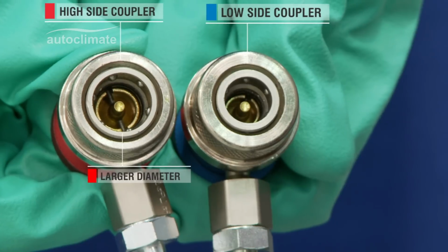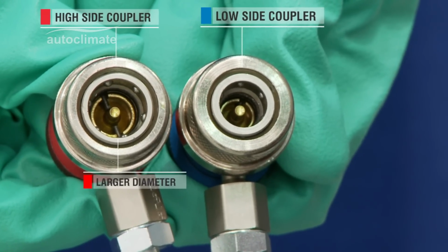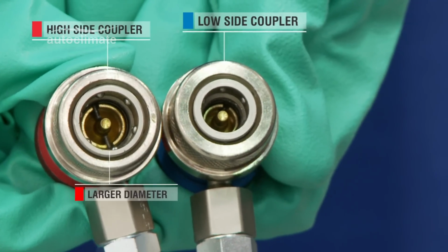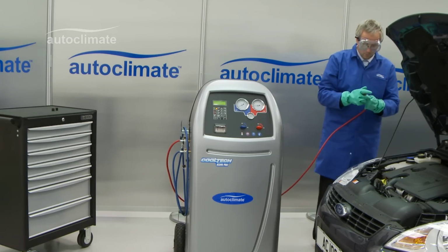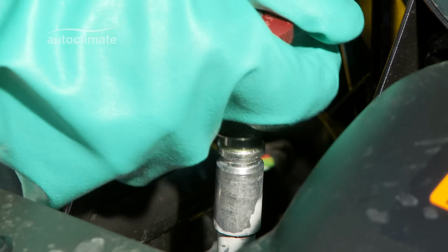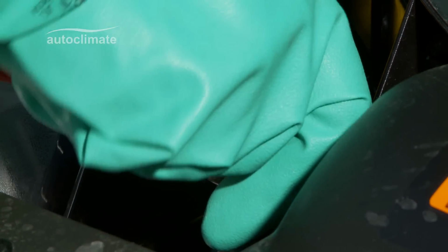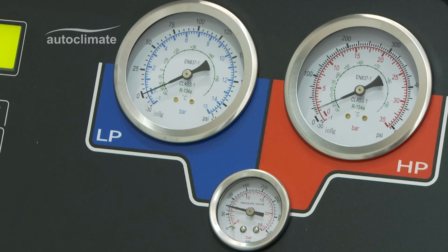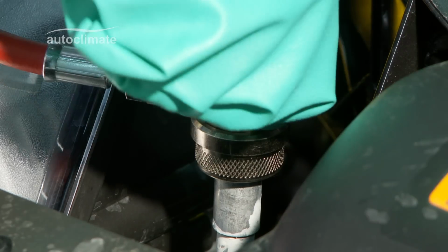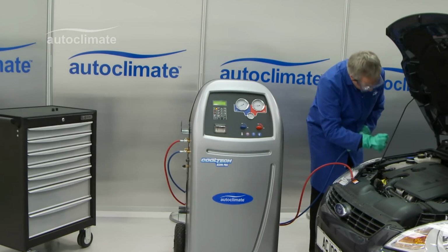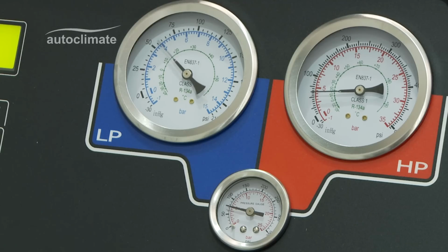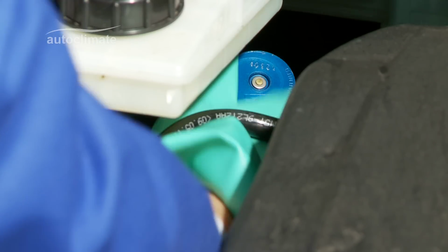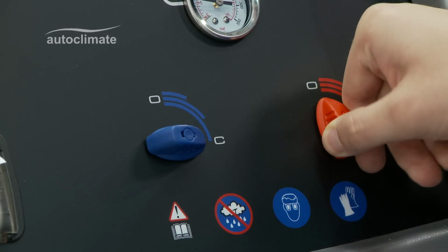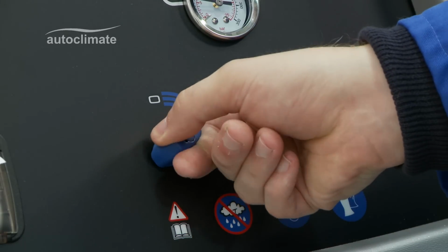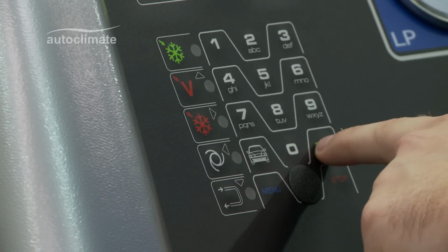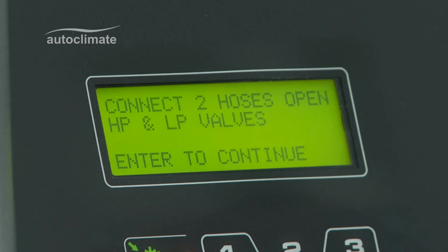To prevent misconnection, the larger diameter red coupler is for the high side and the blue coupler for the low side, and that has a smaller internal diameter. Open the high and low pressure panel valves. Press Enter to continue. The machine's compressor starts.